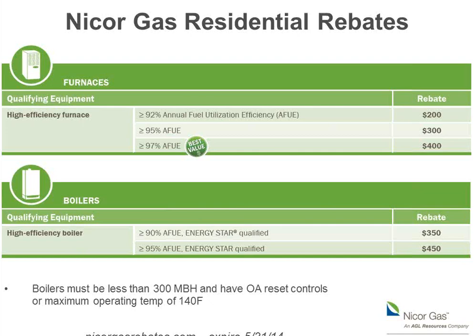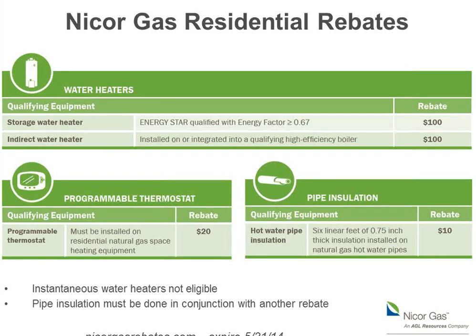So you got to kind of pay attention to that. Don't look at the old specs. Look at the AHRI current website to make sure you got the right boiler there. You do have to put outside air reset controls on those boilers to get that efficiency level, so pay attention to that as well. All the Nicor Gas rebates, by the way, expire May 31st of next year, and then in June a new program would start. Pretty much every June new programs start for most of the Illinois utilities anyway. For Indiana, Wisconsin, Michigan, and other states, it's usually at January 1st.